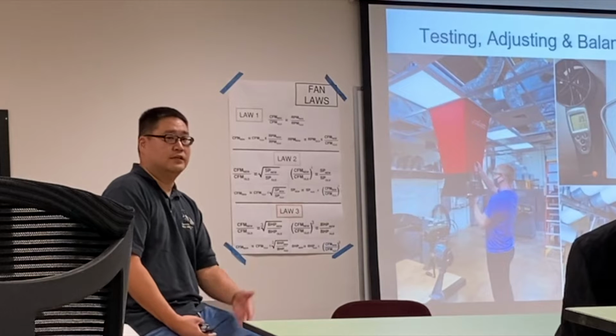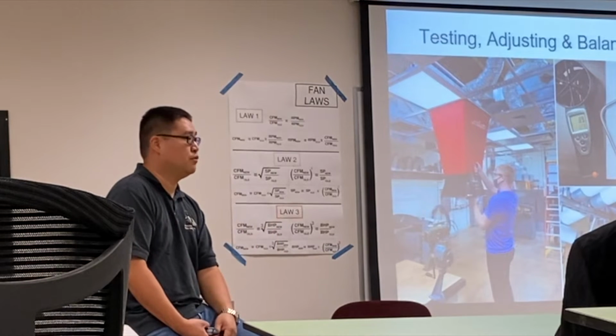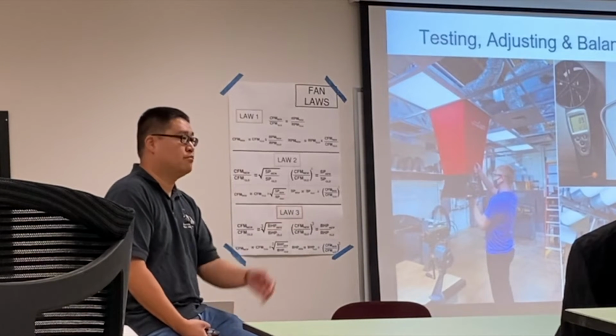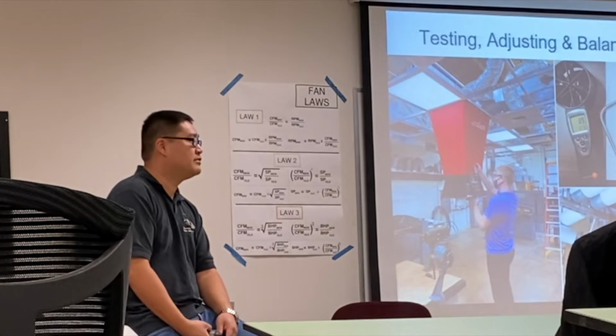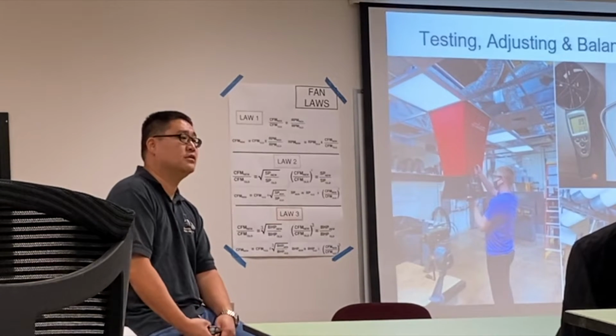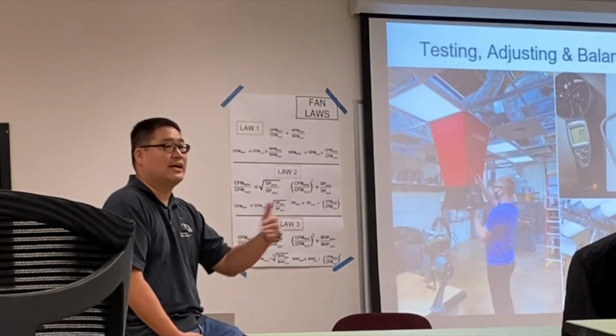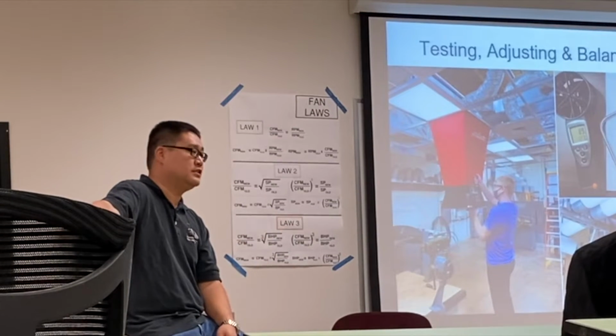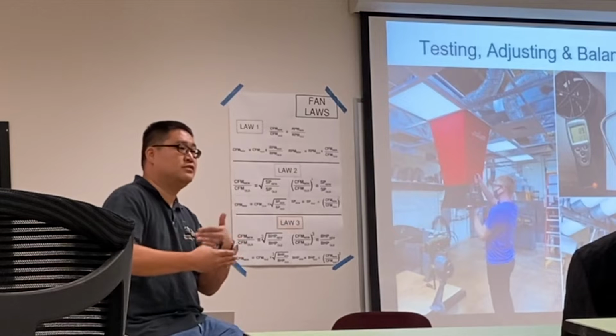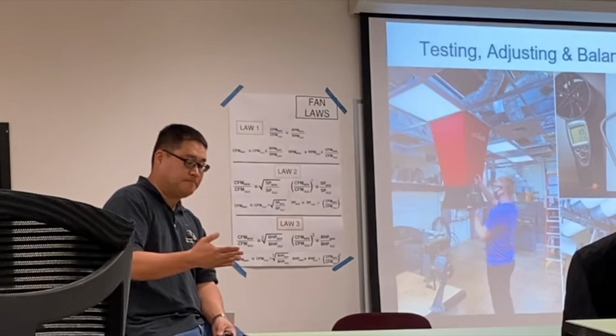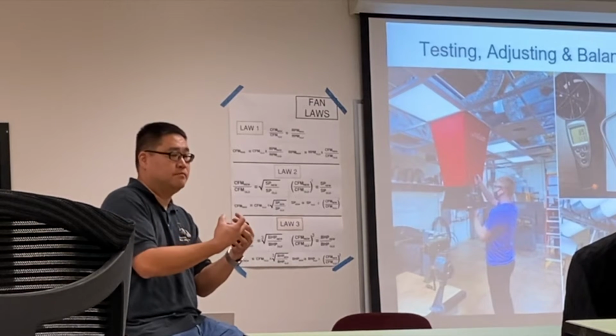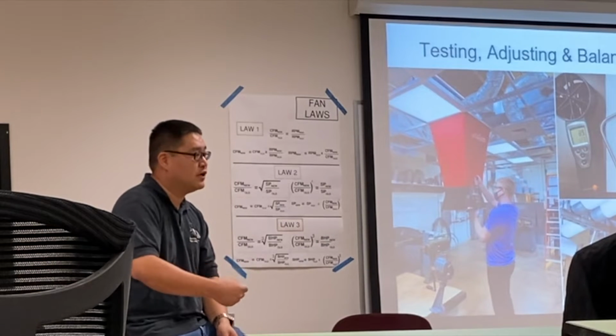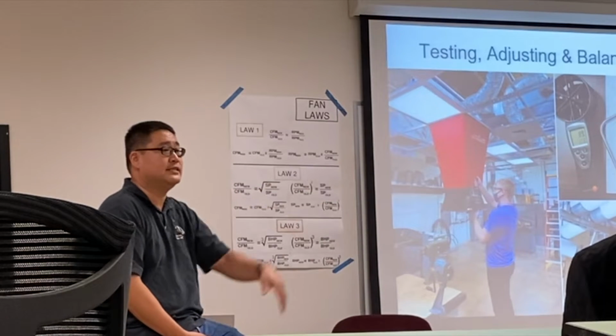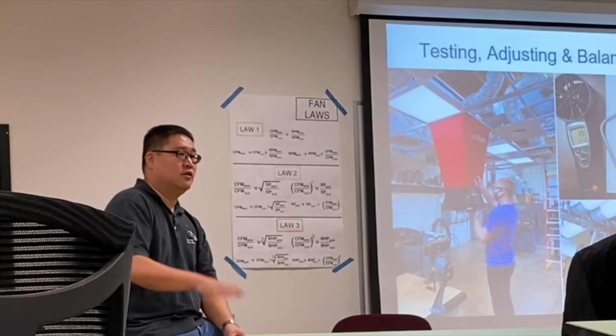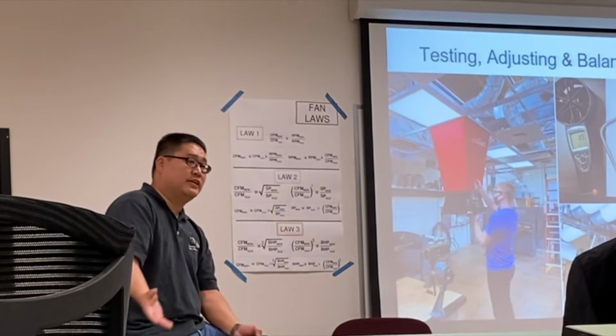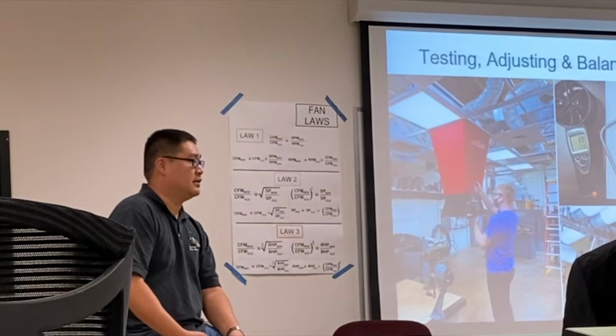The fire life safety system is really important. Air balancing handles pressurization of shafts and emergency exits. Usually when a fire happens you can't use the elevator, you use the stairway. But if the pressure is really different, it creates so much negative pressure that when you try to open the door, it won't open. So when you try to run out to the exit, there's so much pressure that an old lady or a little kid will try to open the door and think it's locked, even though it's not.